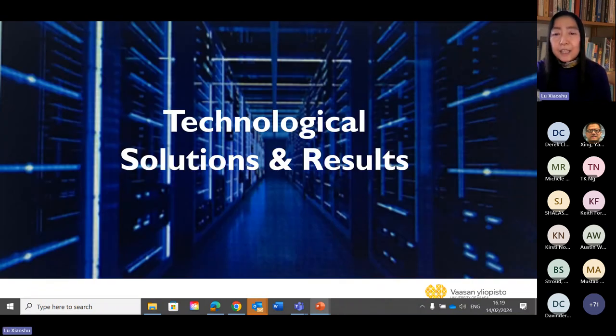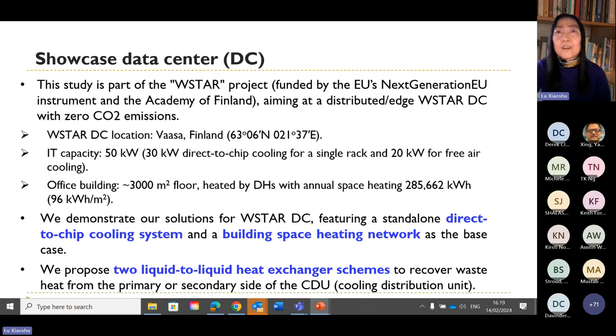Okay, now I showcase our invention using a real data center. This data center is called W Star data center. It is an edge or distributed data center located at our university in the western part of Finland, with IT capacity 50 kilowatts, including 30 kilowatts liquid cooling or direct-to-chip cooling. The heated building is an office building that has about 3,000 square meters floor area heated by district heating. The heating demand is about 96 kilowatt hours per square meter.